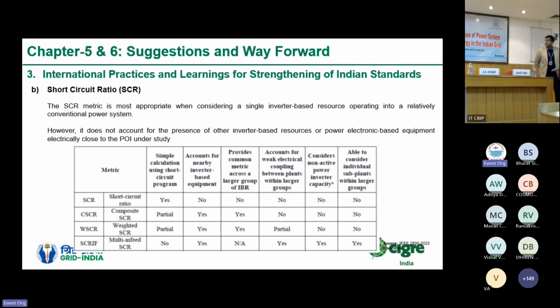It simply does not consider the impact of other inverters nearby that particular inverter. Suppose an inverter is getting integrated at one point; its behavior and its interaction with other nearby inverters should be studied, but the adoption of the simple short circuit ratio term fails to acknowledge this. Other metrics like composite short circuit ratio, weighted short circuit ratio, and multi-in-feed short circuit ratio have added advantages, and multi-in-feed short circuit ratio has been found to be most appropriate to identify the interaction with other nearby inverter-based resources.